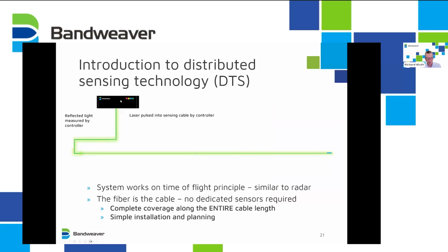So you have the controller, you have the fiber optic, which goes into the installation, and the controller sends pulses very rapidly into the fiber, up to about 20,000 pulses per second, and then it's very rapidly sampling the reflected light back, hundreds of thousands of times per second. By measuring how long it takes the light to get back, you can pinpoint where that information has come from to within about half a meter. Typically for fire detection, we set it up for 1 meter.